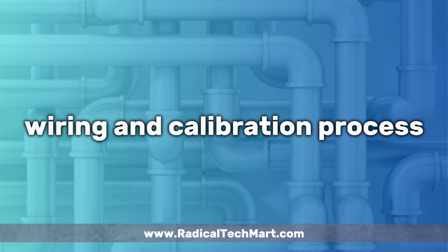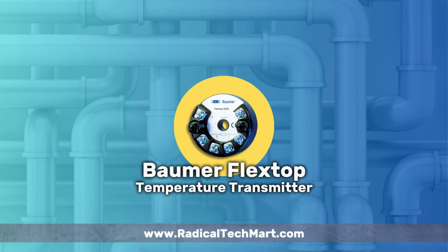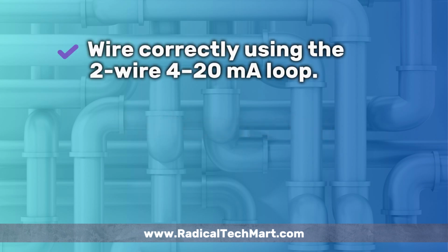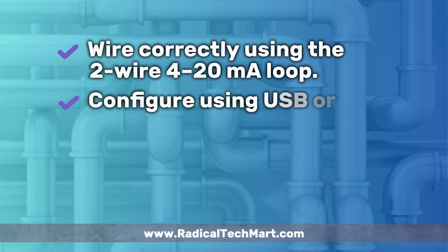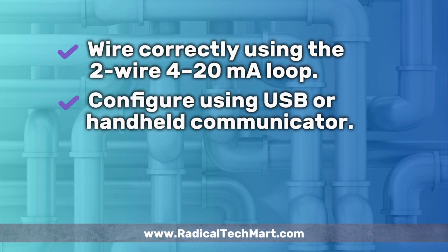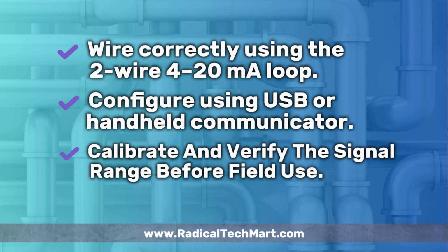So, that's the complete wiring and calibration process for the Baumer Flextop series transmitters. To summarize, wire correctly using the 2-wire 4 to 20 mA loop. Configure using USB or handheld communicator. Calibrate and verify the signal range before field use.